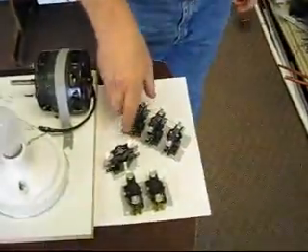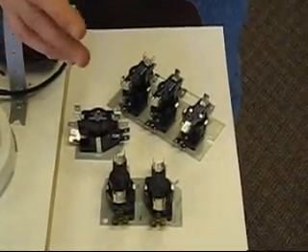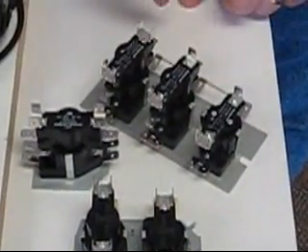Below me are several common types of sequencers. What a sequencer is, is a series of switches. The bottom terminals are 24 volts, they turn on a switch, and all these switches come on in sequential order, hence the name sequencer.